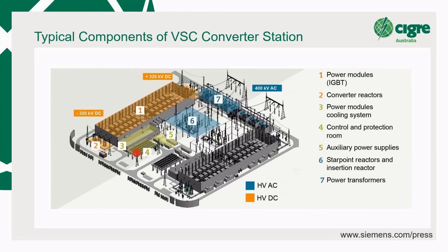And cooling, as I mentioned before, there's a lot of switching going on, so a lot of heat loss is generated, and these here are cooling towers and cooling equipment. And that's typically what a converter is. The interface transformers, or the converter transformers, are over here, connected to a bus bar. And it may very well be an MMC, but you may have some pretty tight harmonic requirements, so there may be some filtering in there. It really depends on your application.